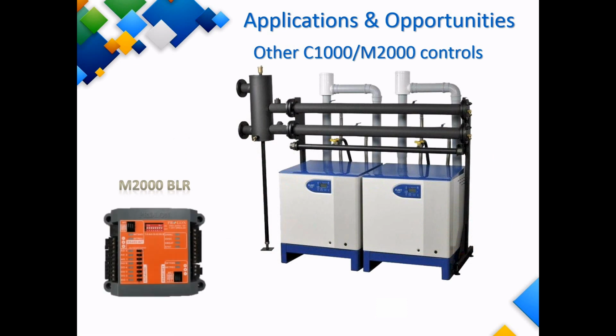Prolon offers a robust boiler controller, which can control up to 4 boiler stages and 2 pumps. The boiler stages and pumps each have lead lag and equal runtime sequences, as well as a failover sequence for redundancy purposes. So in case a pump fails, the backup pump will turn on. This device can also control up to 2 modulating boilers. This controller has an outdoor reset in case we wish to have the hot water set point change depending on the outside air temperature. Other included features are warm weather shutdown and timers on the outputs to monitor how long each piece of equipment has been running.